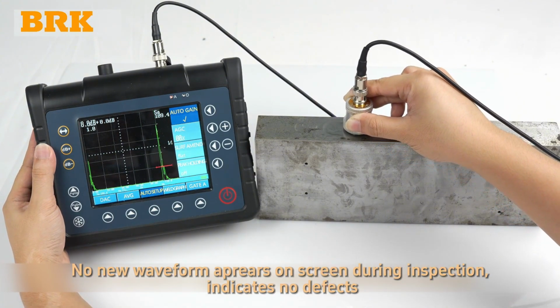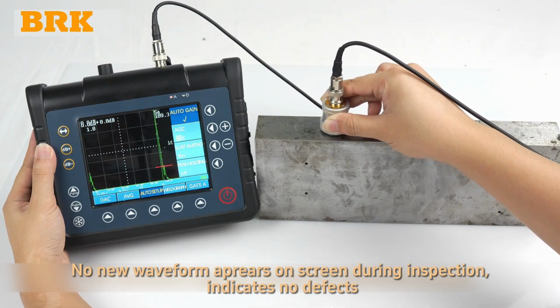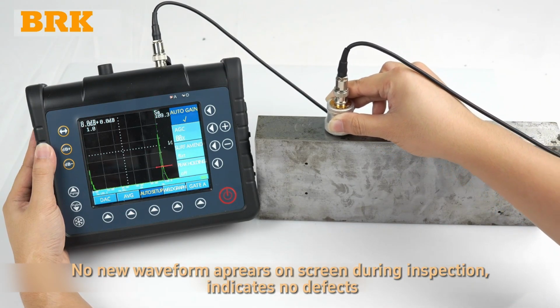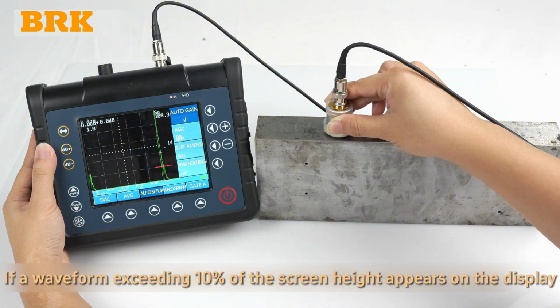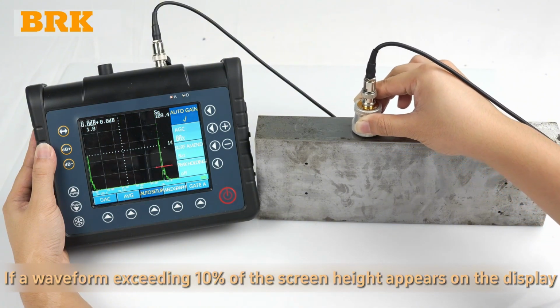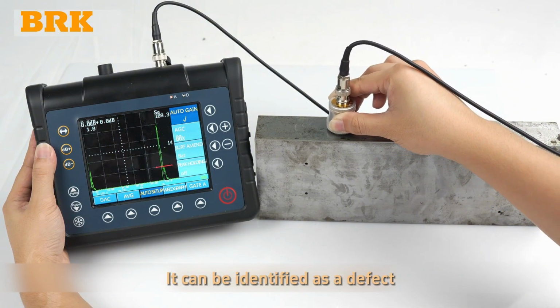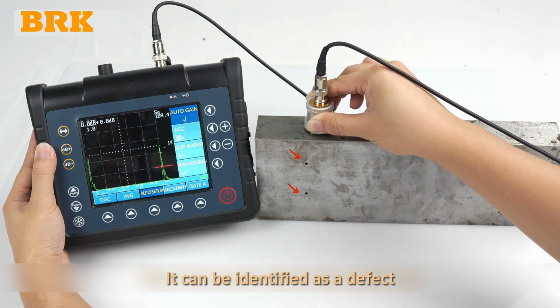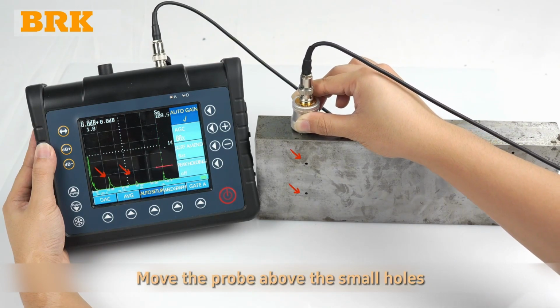No new waveform appears on screen during inspection. Indicates no defects. If a waveform exceeding 10% of the screen height appears on the display, it can be identified as a defect. Move the probe above the small holes.